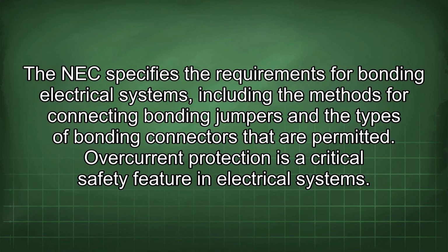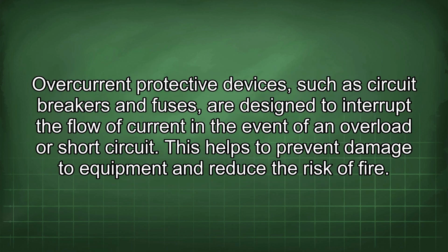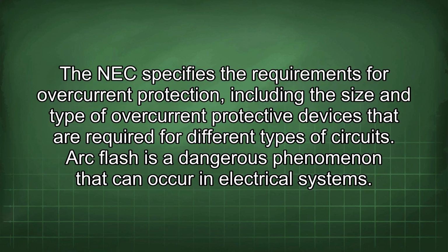Overcurrent protection is a critical safety feature in electrical systems. Overcurrent protective devices, such as circuit breakers and fuses, are designed to interrupt the flow of current in the event of an overload or short circuit. This helps to prevent damage to equipment and reduce the risk of fire. The NEC specifies the requirements for overcurrent protection, including the size and type of overcurrent protective devices that are required for different types of circuits.